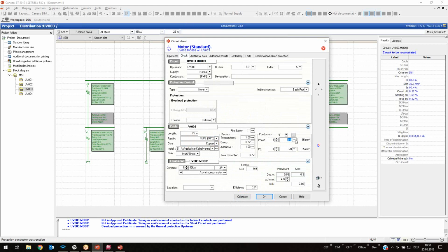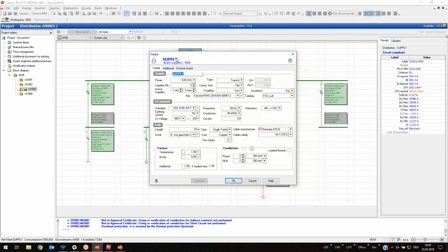Yeah, you can. Correct. First of all, here you have the AWG cross sections. You see, if I choose the AWG10, it's 5.26 square millimeters for the calculation. That's a good thing. The second thing, you can on the transformer or on the source choose 460 also. Yeah, here the 60 hertz. You can choose a voltage level regarding the US market, and so you have the Eckparameter in German. So it's the most important parameter for the calculation. But of course, the standard is different.